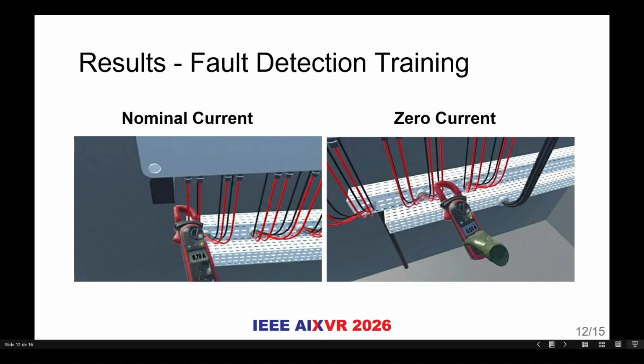On the left image, the user measures the first string. The clamp meter shows 8.79 amperes, which represents the nominal current. This indicates that the specific part of the system is working correctly.